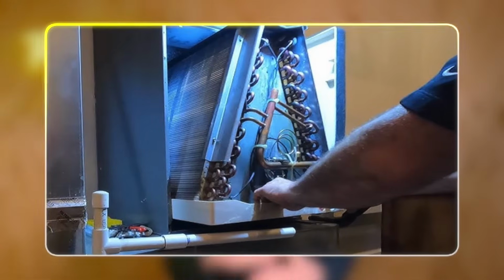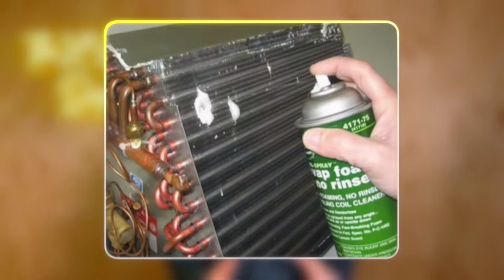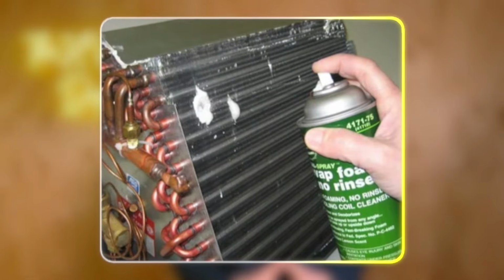And the easiest way to do this, again, this is something that's typically performed by a technician, so I don't advise you do this, but you at least know what's going on. If you have a dirty evaporator coil, it's basically as simple as, and sometimes it's not so simple to actually access the evaporator coil, but you'll pull off the service panels for the evaporator coil, inspect it, see if it is in fact dirty, and if it is, there's a cleaning solution that you can use on that. The big thing is you don't want to damage the fins or the coils. Again, I don't advise you to do that, but that is a very common problem that will cause your system to ice up if it gets dirty to the point that your system just has very poor airflow. It's going to ice up.